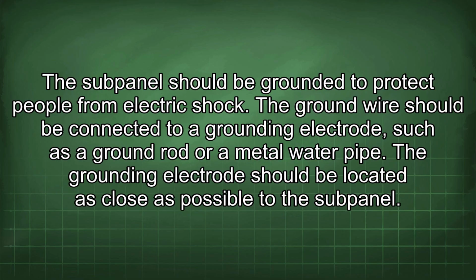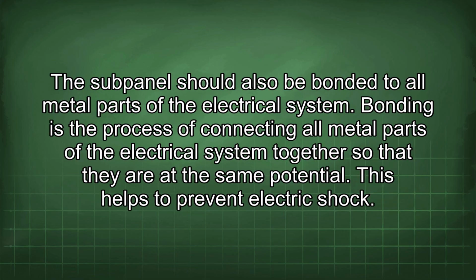The subpanel should be grounded to protect people from electric shock. The ground wire should be connected to a grounding electrode, such as a ground rod or a metal water pipe. The grounding electrode should be located as close as possible to the subpanel. The subpanel should also be bonded to all metal parts of the electrical system. Bonding is the process of connecting all metal parts of the electrical system together so that they are at the same potential. This helps to prevent electric shock.